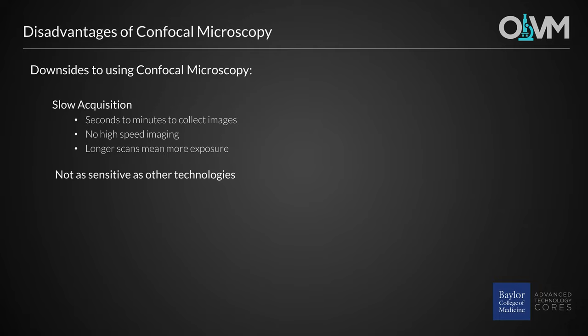This can be somewhat problematic, because confocal microscopes aren't the most sensitive instruments compared to other technologies like CCD-based imaging systems. So fragile live specimens, or specimens with weak fluorescence, low QE reporters, or fluorophores that bleach quickly can be troublesome to image with a point scanning confocal microscope.